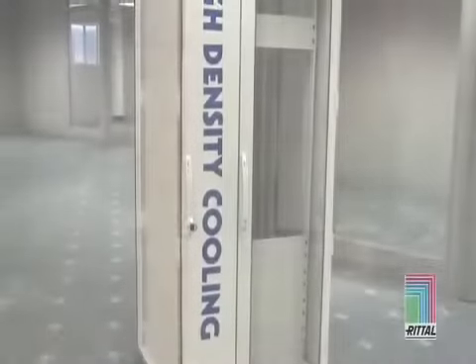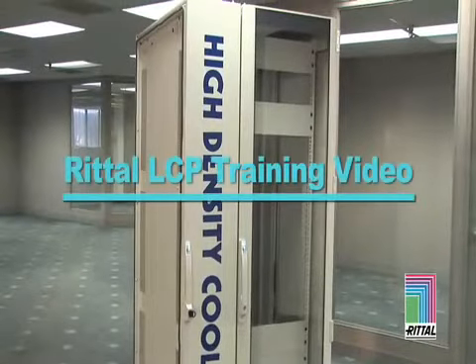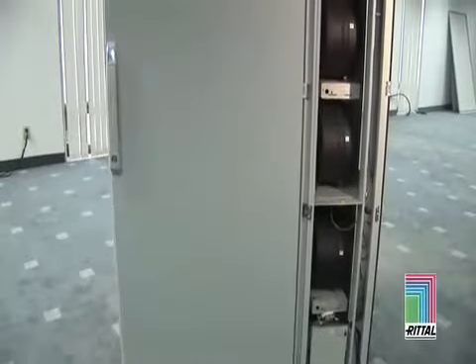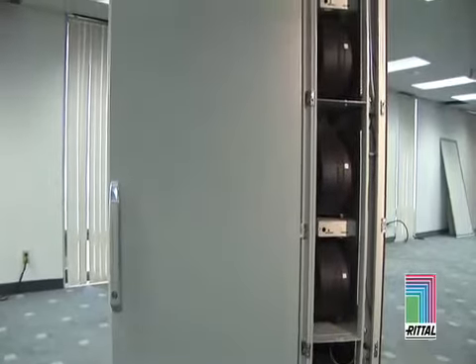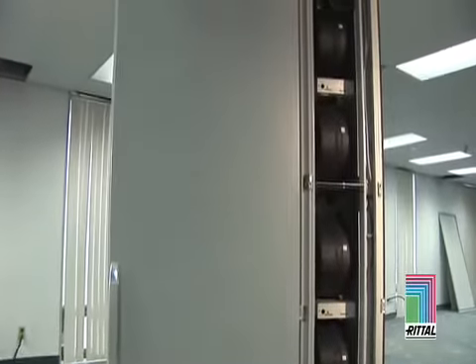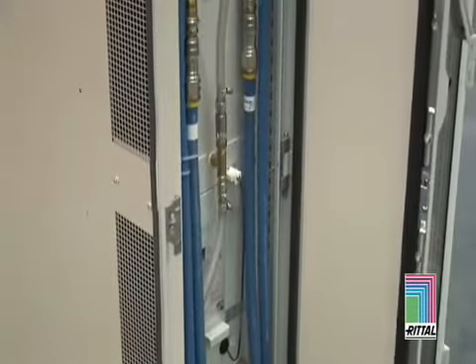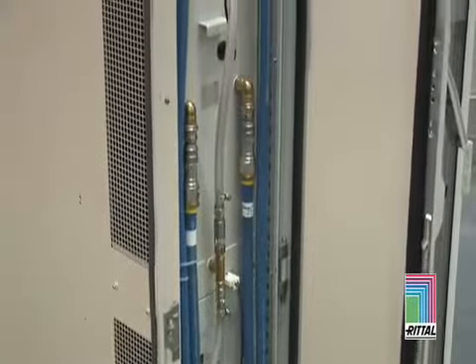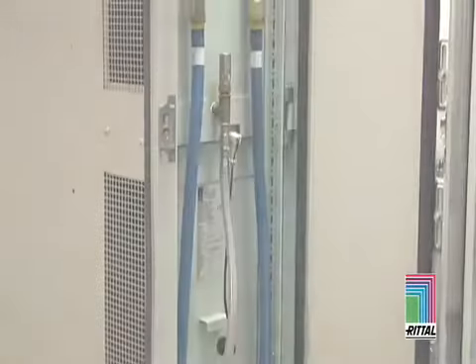Introduction to the Rittal Liquid Cooling Package, also known as the LCP. The LCP consists of three high-performance water-air heat exchangers, three fan module pairs, and an environmental control system to manage and report the operation of the unit. These parts give the LCP the ability to cool up to 20 kilowatts of installed IT load while maintaining precise control of the cold air temperature being delivered to the servers.